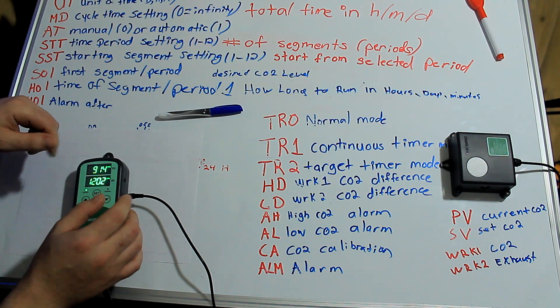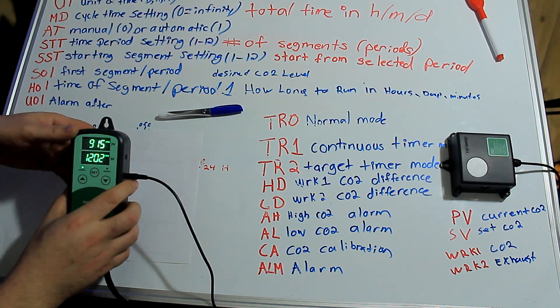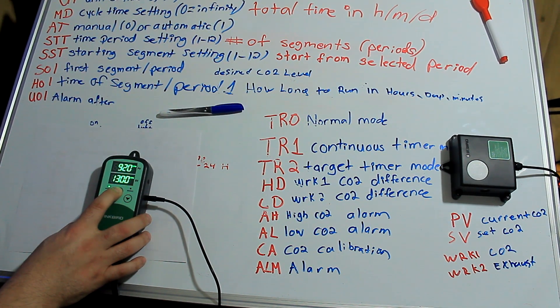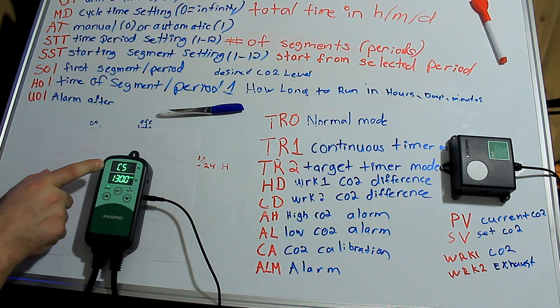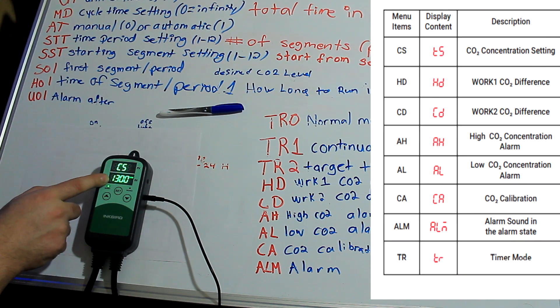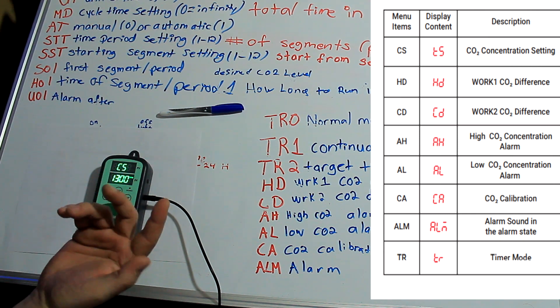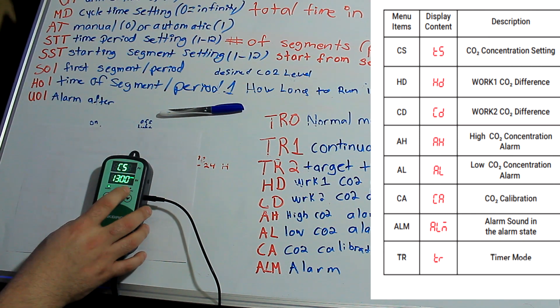Let's get into the TR0 normal mode. What you want to do is hold the set button for about four or five seconds until it starts to flash. The CS is going to ask you what you want to set your parts per million to. 1,300 sounds like a reasonable number, so we're going to hit that.